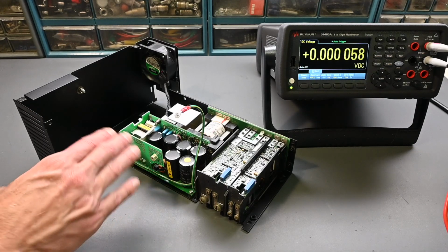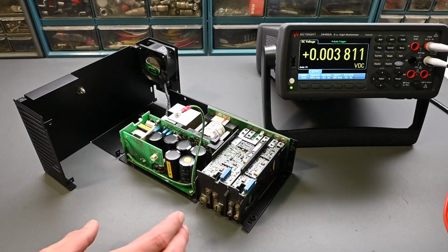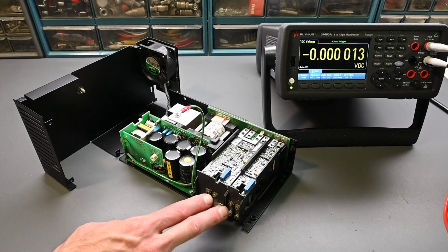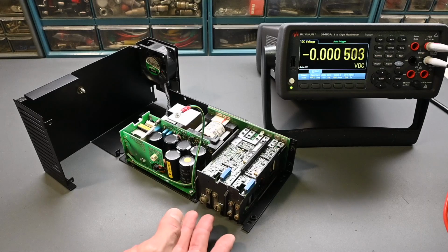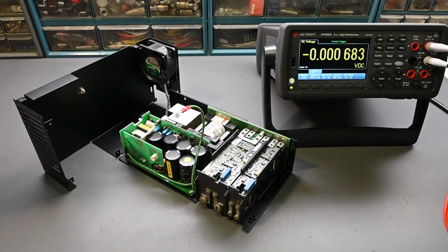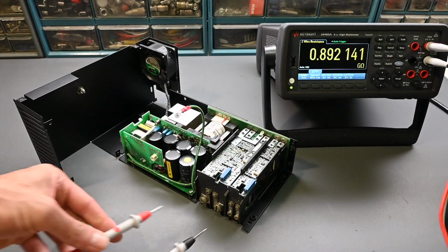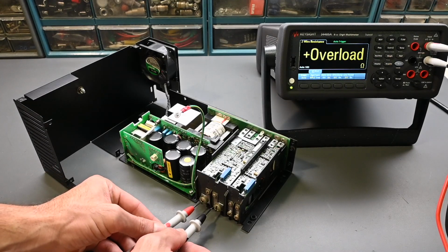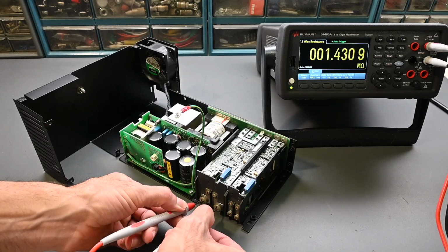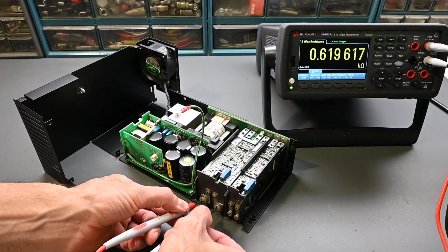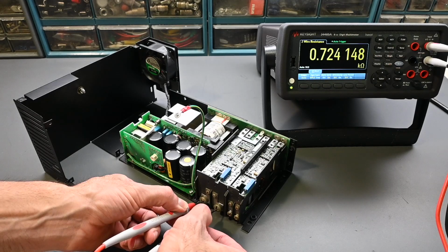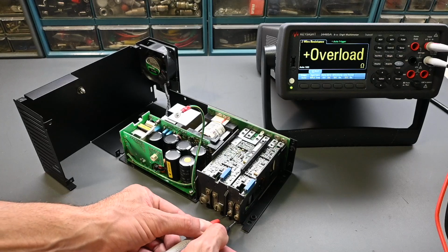Before I start on any further troubleshooting, I should take a quick resistance reading across the output terminals, just to make sure there's no short circuits, because a short circuit could certainly cause it to go into an overcurrent protection mode. So let's put it over to resistance and take a quick reading across here. No problems there, that looks okay. About 725, 726 ohms, no problems with that.